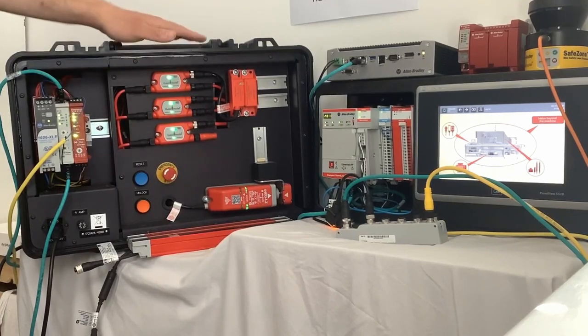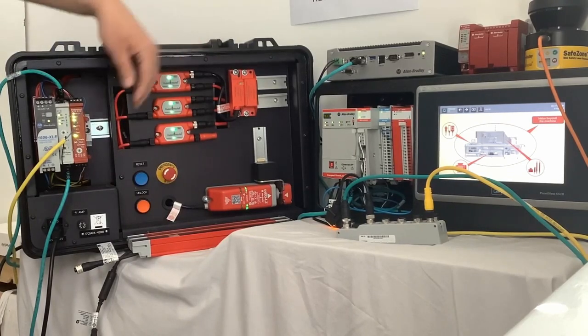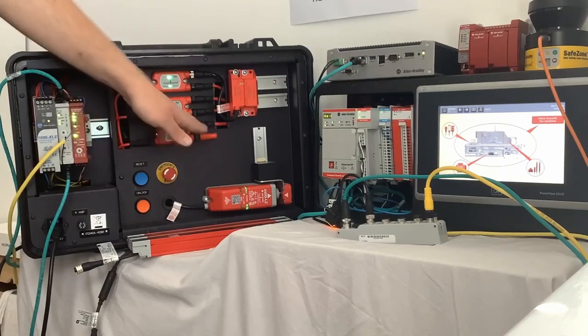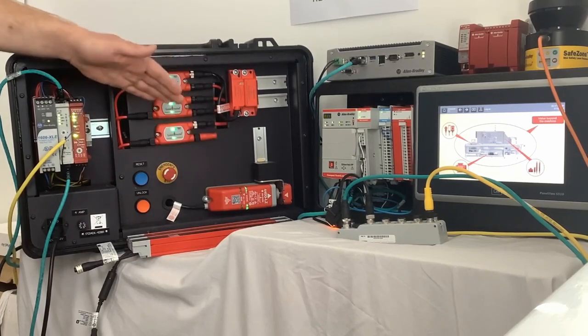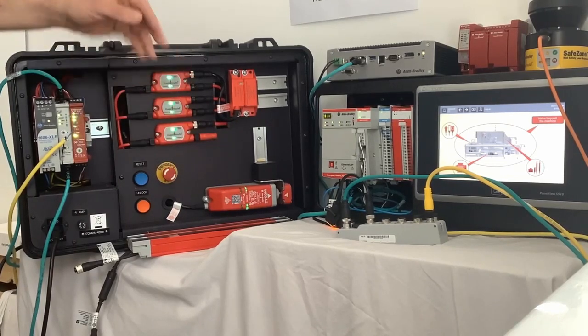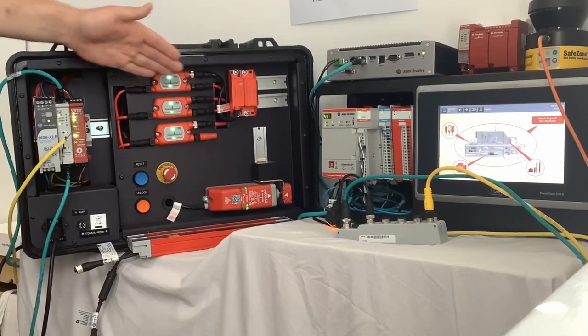Also, if you need to extend this in the future, simply turn the GuardLink relay off, remove the terminating resistor, then add on the new device, repower. That then becomes the next tap in the address. Obviously going up to a maximum of 32 on one network run.